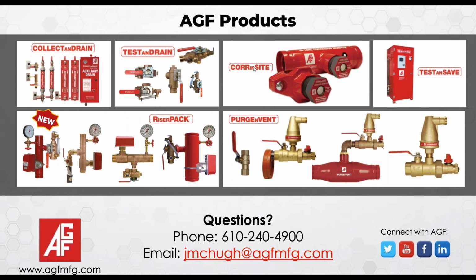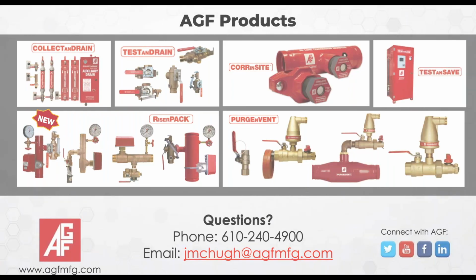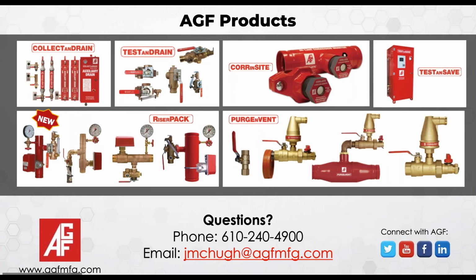because as in talking with numerous customers around the country with these, if we get to the point that someone has pinhole leaks, well, that system has already been ruined. That pipe is already damaged beyond the point of repair. If you have pinhole leaks in the pipe, the only solution currently allowed for fire sprinkler piping is to remove that section of the pipe until you get to satisfactory wall thickness.